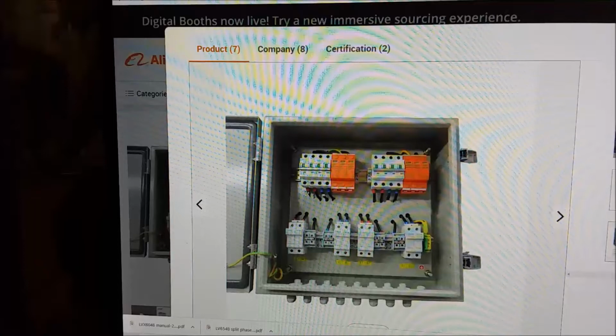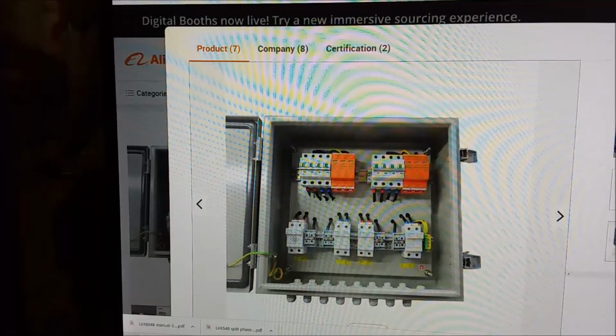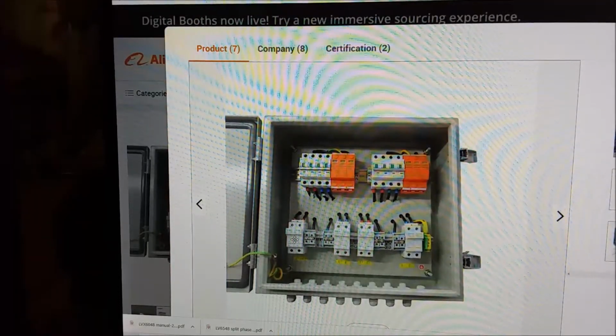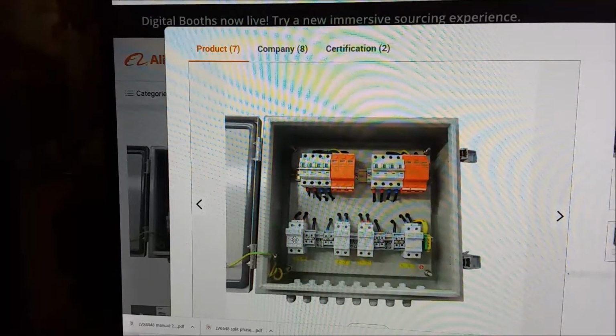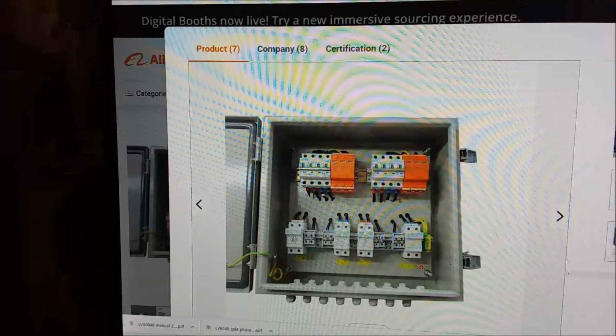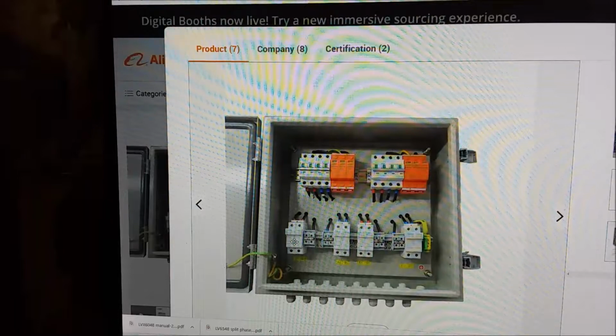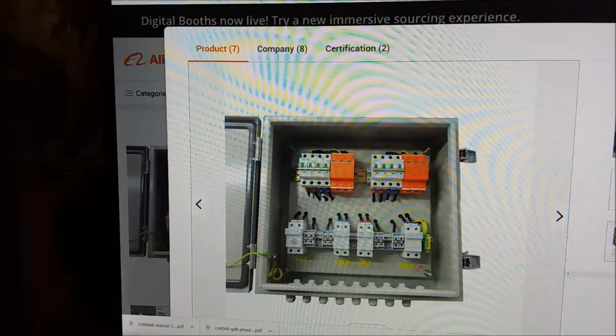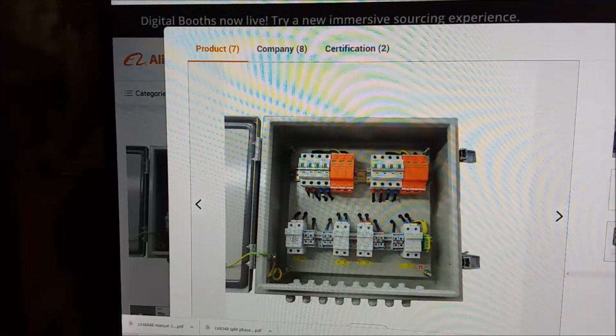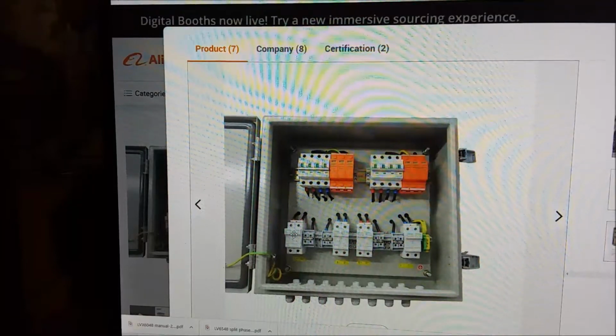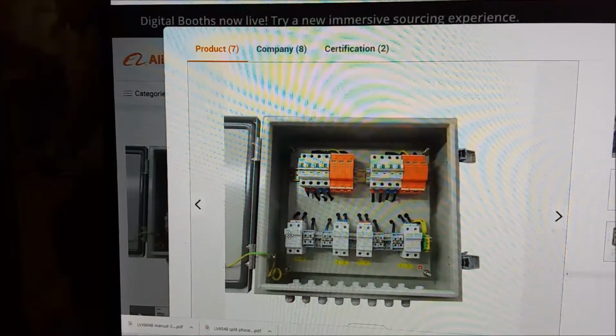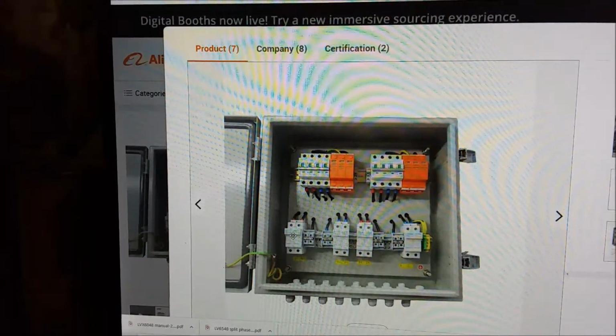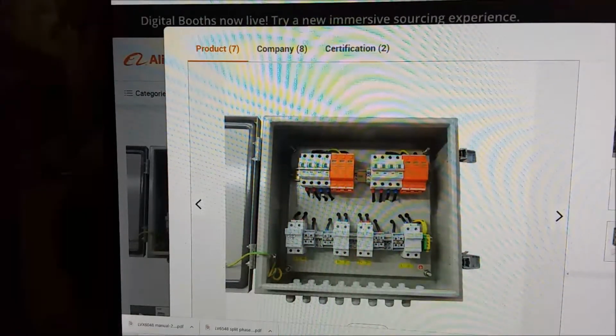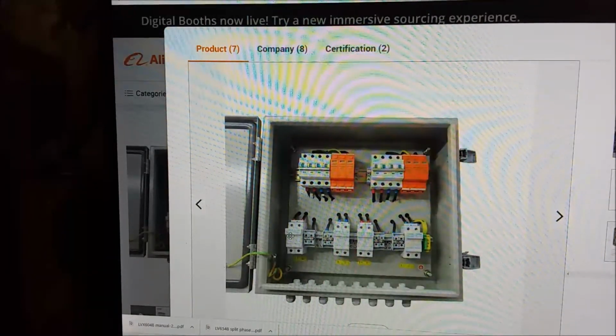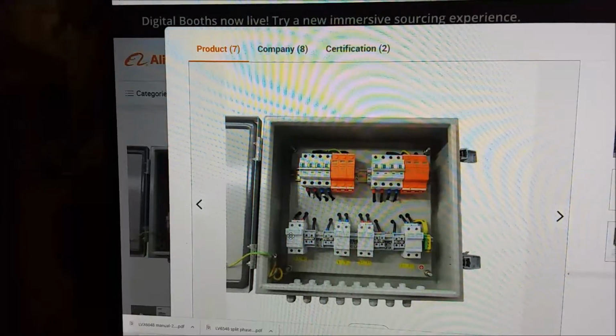Now you have these fuses. Fuses are preferred because they blow instantly. Circuit breakers take a while to load and heat up the metal, melt, and trip, and some of them never trip until the thing is already on fire. But fuses, they're bang, you know. You can get fuses full of sand, called slow-blow, with a real long delay, like a quarter of a second, which can get you in trouble with electronics.